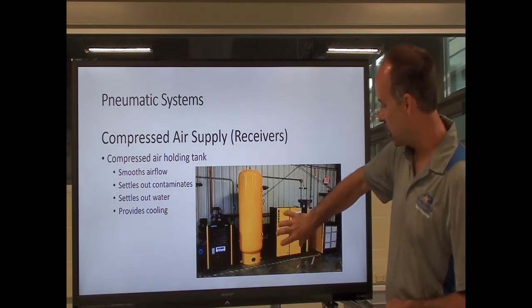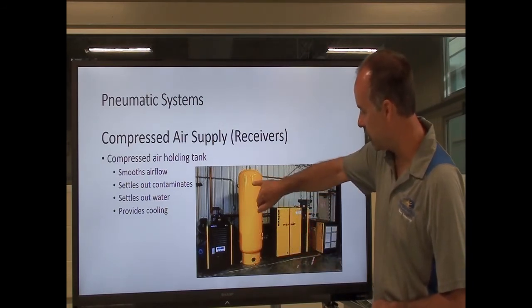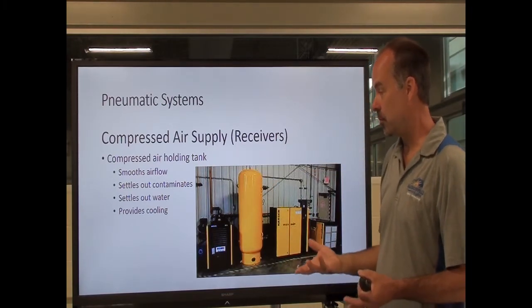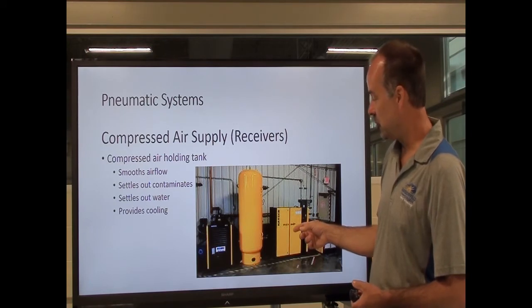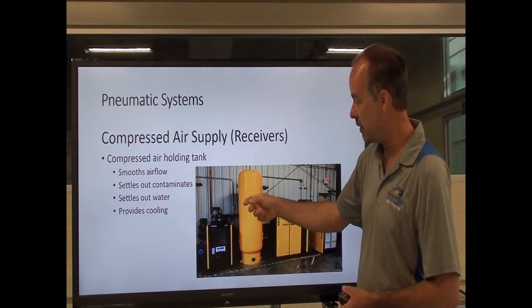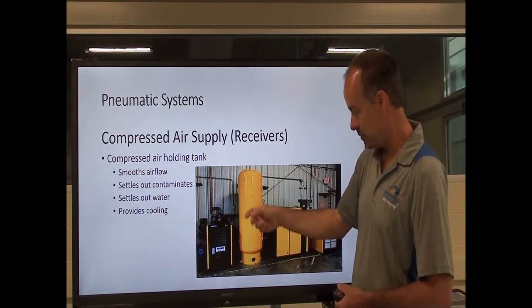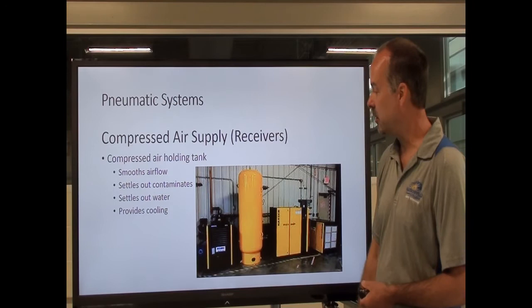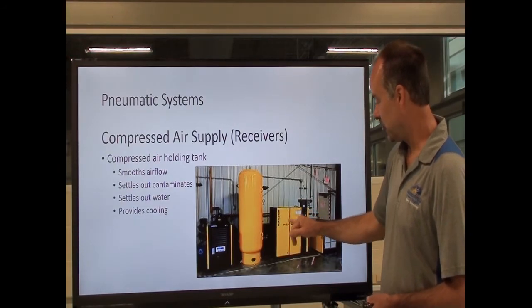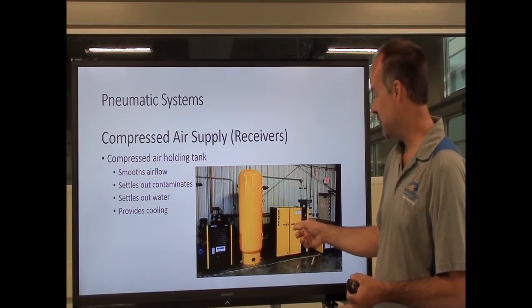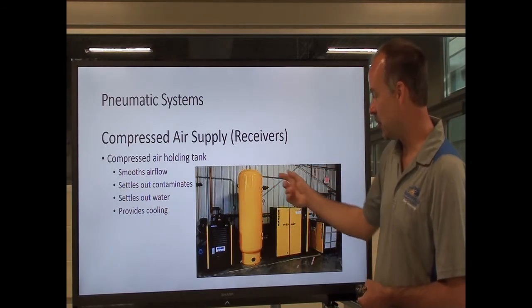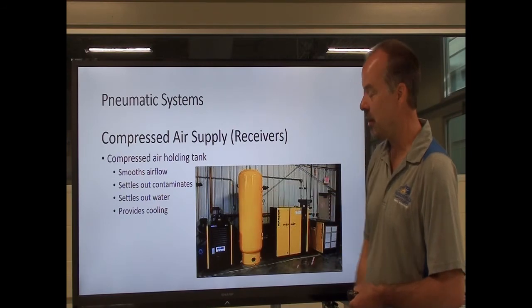Receivers: in this setup we have an air compressor, and leaving the air compressor we come to a receiver. A receiver is just like a large tank that holds compressed air. This allows you a cushion by smoothing out the airflow so you don't have surges — we pressurize this tank, and coming off the tank we have a regulator to maintain pressure on our outlet side. Also, sometimes air compressors have oil inside that gets sent to the outlet of the compressor; the receiver allows a place for that oil to settle out to the bottom, giving you cleaner air coming out.